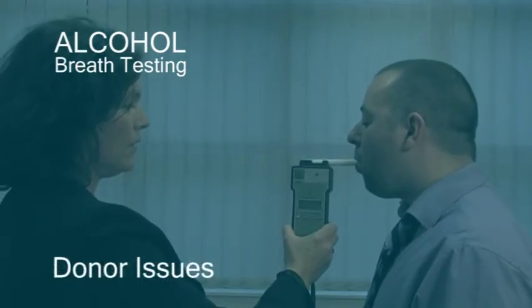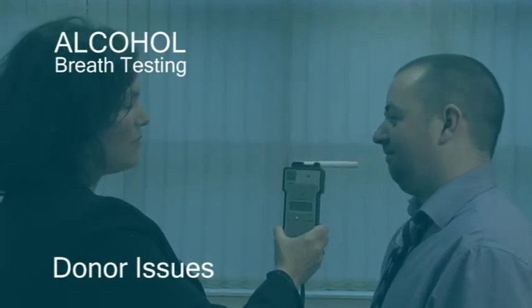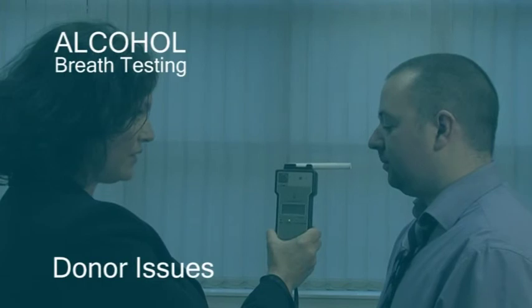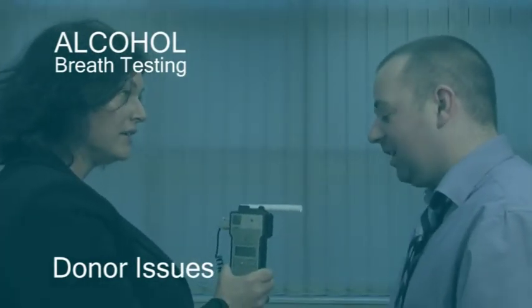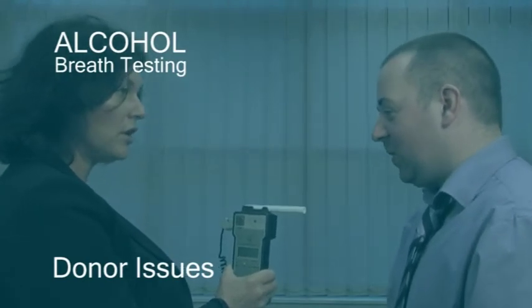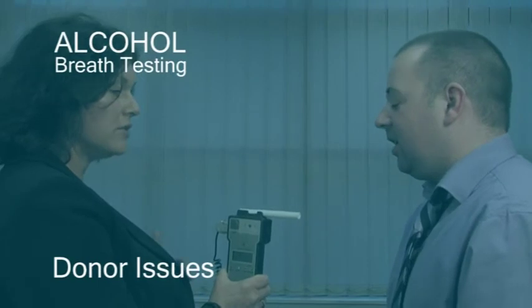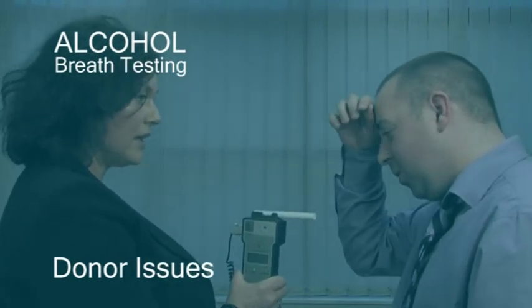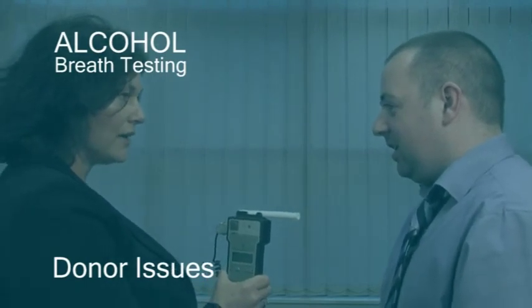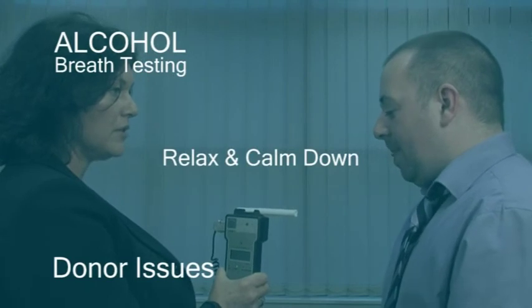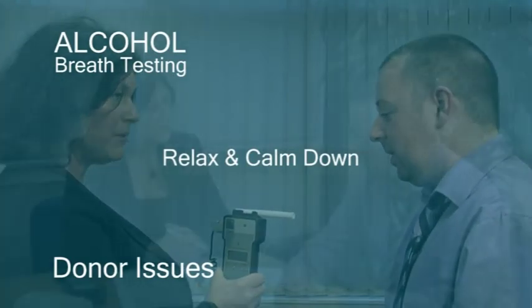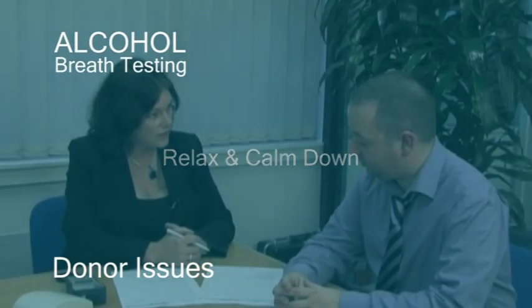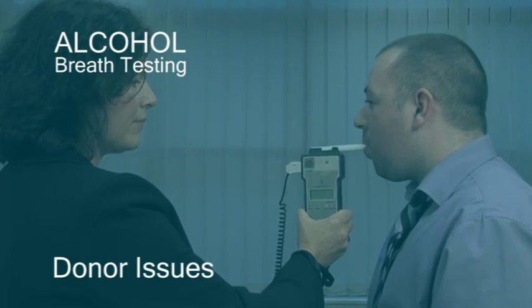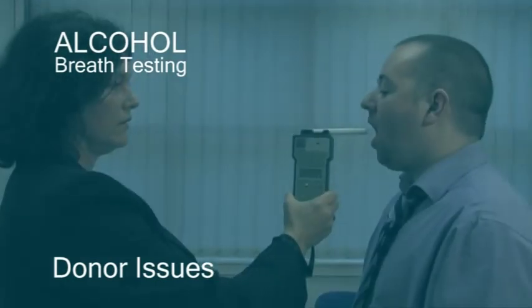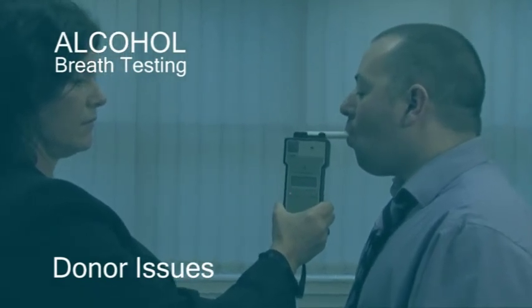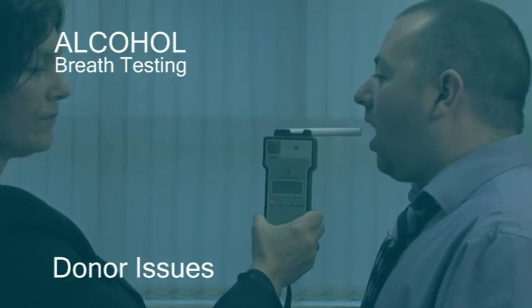Donor issues. From time to time, donors will have genuine difficulty providing a specimen. Because the machines detect airflow, they will identify the pattern of someone with poor lung capacity, such as an asthma sufferer, so these are not usually a problem. However, often the circumstances of an alcohol test mean the individual is agitated and hyperventilating to the point where they cannot provide a specimen. They need time to relax and calm down. Some people take time to adjust their blow to suit the machine and may get a couple of abort signals before they succeed in providing a suitable specimen. Another common fault is people taking a deep breath ready to exhale, but doing this when they are already using the mouthpiece. This will also result in an abort message.